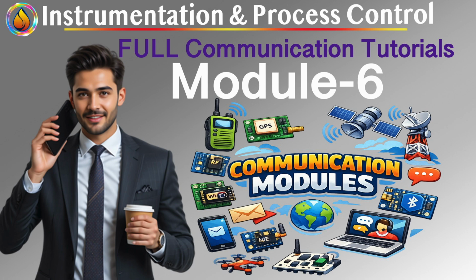PROFIBUS DP, when time matters more than detail. DP stands for Decentralized Peripherals, and that name tells you everything. PROFIBUS DP was built for fast cyclic data exchange, time-critical I/O, distributed peripherals close to the process. Think of devices like remote I/O racks, motor starters, drives, valve islands. These devices need rapid updates, predictable timing, minimal overhead. DP achieves this by using a streamlined protocol stack, focusing on cyclic data, eliminating unnecessary OSI layers.